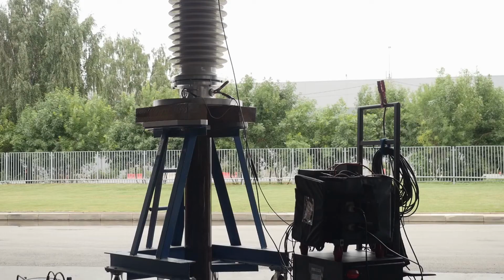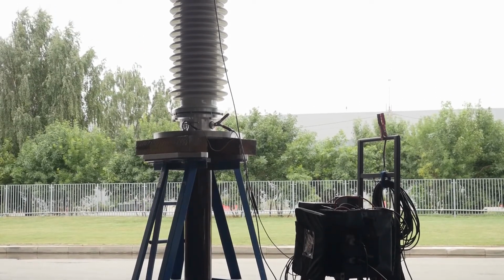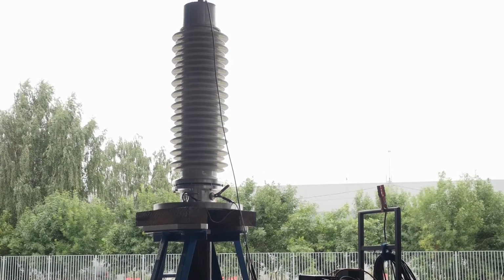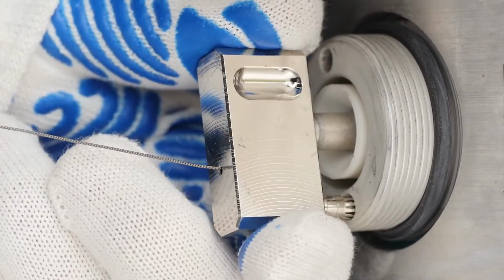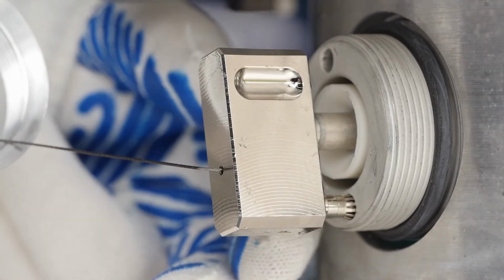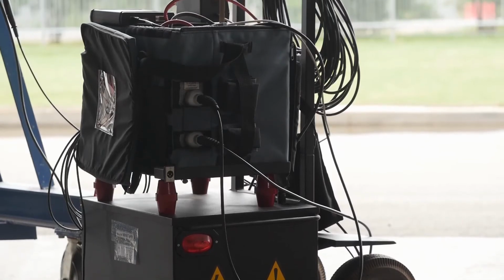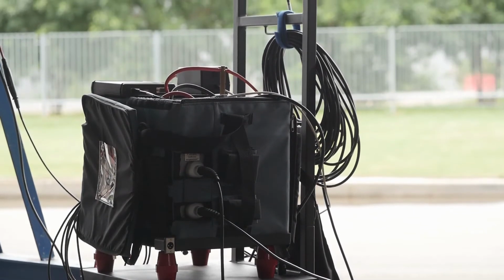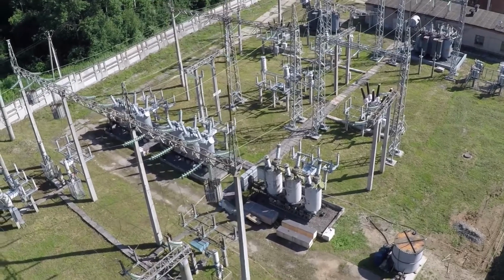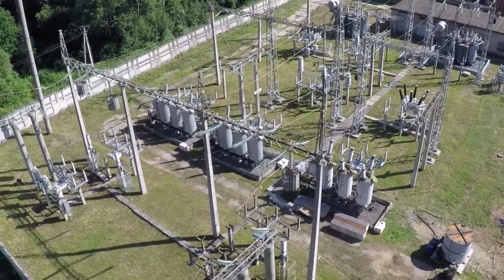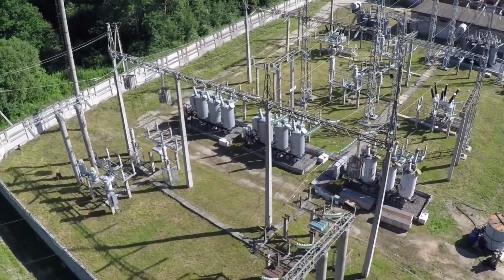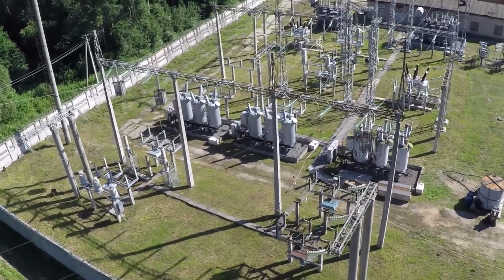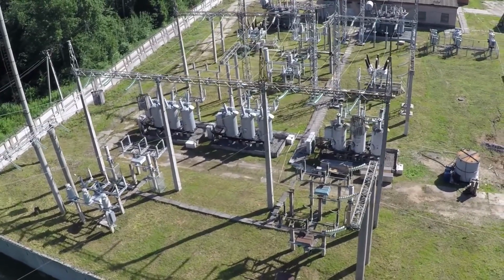In order to ground the test tap, install the multi-contact so that the pin would enter a central hole of the contact and a spring-loaded contact would match the test tap hole. At this moment, visual and instrumentation monitoring of the ground reliability can be done, although there is no need in this procedure when the multi-contact is installed correctly. Afterwards, screw the test tap hood on manually, pressing on the rubber sealing ring on the test tap body. This quick, however demanding procedure of the test tap grounding shall allow eliminating one of the main causes of high voltage bushing damage. Thus, we have checked the condition of the internal insulation of the bushing.